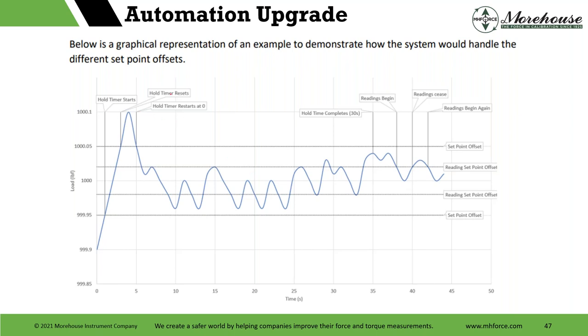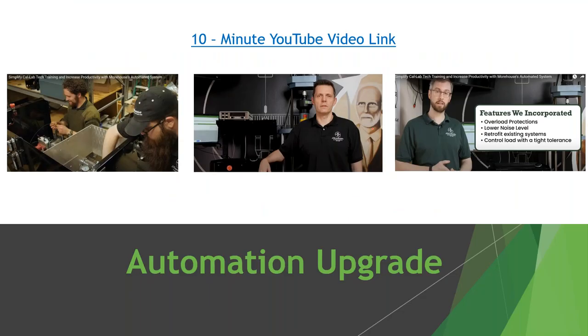It's not a hold timer reset. Hold timer restarts at zero, and while it's within this 1,000 pound, it's taking 30 seconds. Readings begin right here, and this is the window. 1,000 right here, the window was set to plus or minus 0.5, and that's the readings, and then getting an average of those readings. We have a 10-minute video on YouTube explaining it.